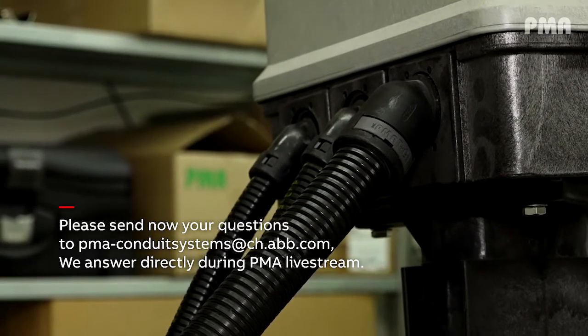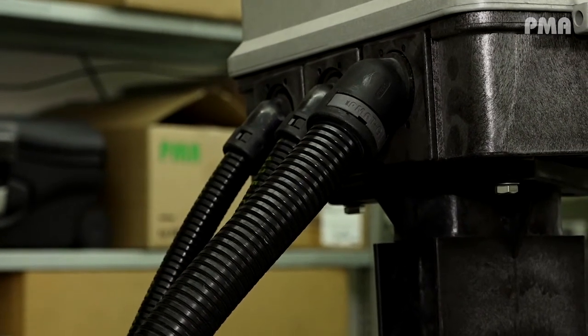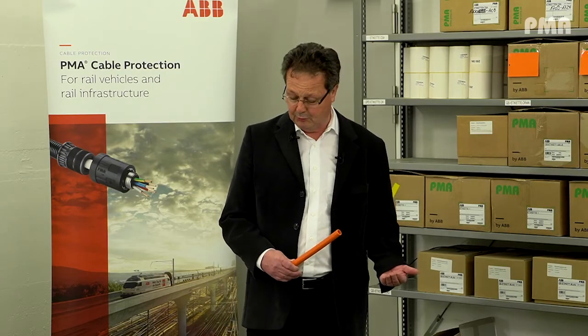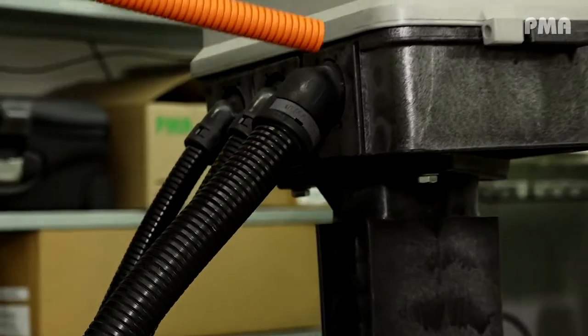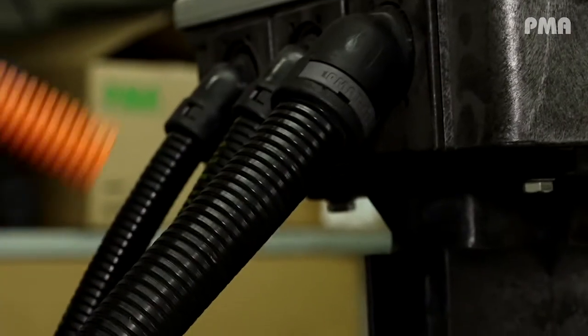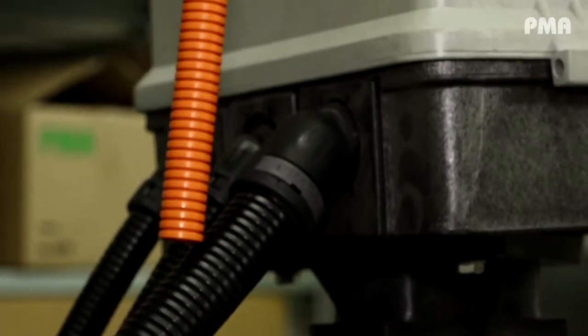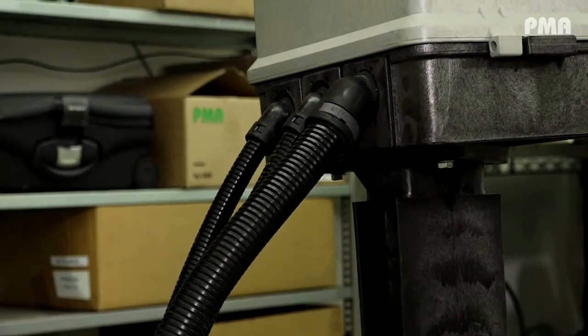What I was also talking about was in regards of the ingress protection. This is at the end for me a little bit the key, because with the ingress protection you define what kind of fitting to use. But ingress protection you cannot influence at the end, but the installation can be influenced. That's why we always try to go with the corrugated conduit in the direction of the ground. Why? Because if water is coming down here, falling on the system, it ripples just away. If I would do it upside down, so to say, the water will stay on the fitting. You saw the picture before with all this ice.